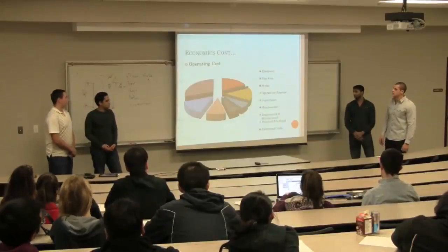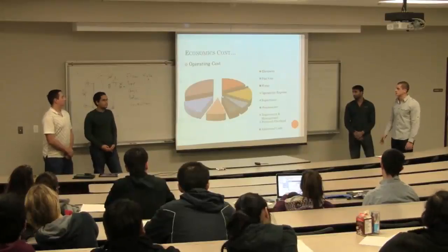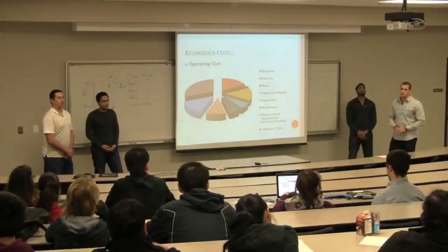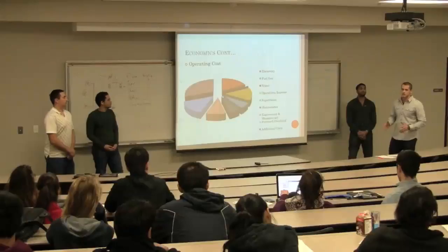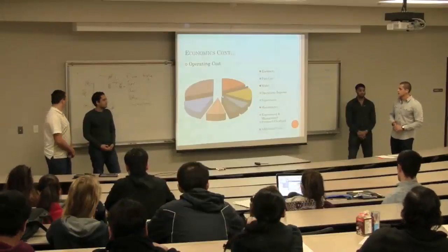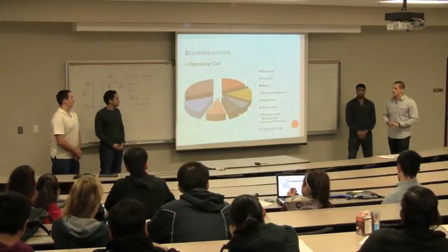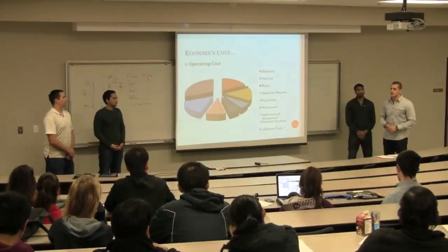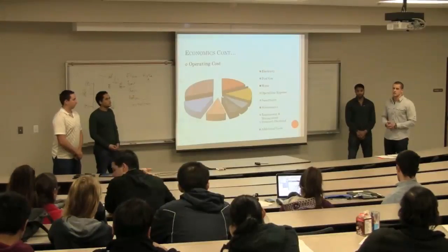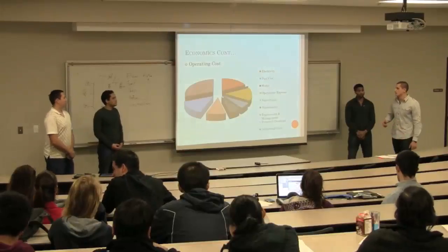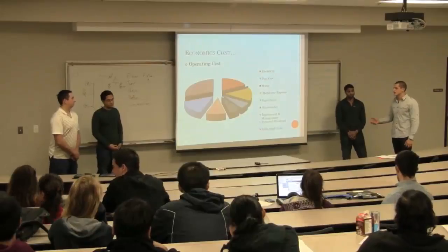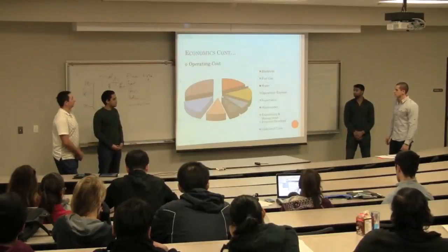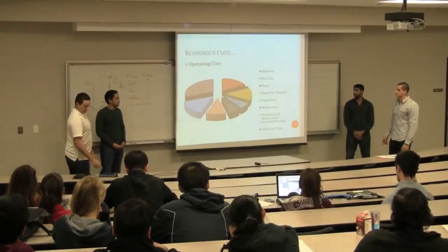So the yearly operating cost of the plant was determined to be approximately $7 million. A large majority of its operating cost was due to the electricity requirements of the centrifugal pumps. Many of these pumps had large motors in the range of 2,500 horsepower. The fuel gas and water supplied to the furnace was actually very minimal because the SAGD process actually produces a lot of natural gas, and the amount of steam injected is less than the amount of water that's produced. So they capture this water and the natural gas and feed it to the steam generation unit. The other costs here are just the typical fixed costs, such as maintenance, supervision, operations, engineering management, and so forth.